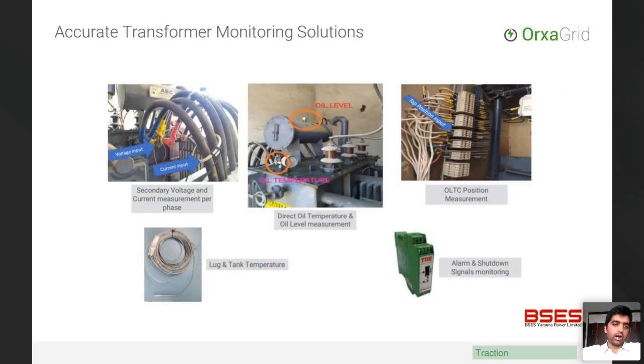A few indications of how we did the monitoring. For the voltage and current measurements, for voltage, we tapped the bushings directly. We tapped the bushing through a voltage tap to get the readings. Since these are secondary transformers, 11 kV by 440 volts, the phase voltage is only 220 volts, which is directly taken into our device. For the current measurements, because these are at the 440 volt side, the currents are typically very high per phase, maybe 200, 300 amperes or even more.